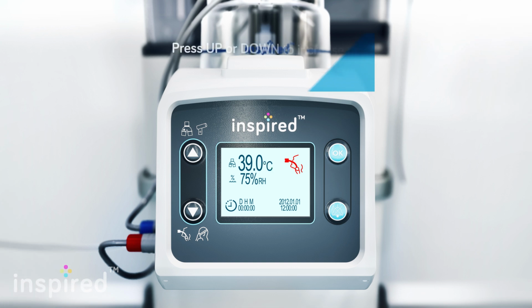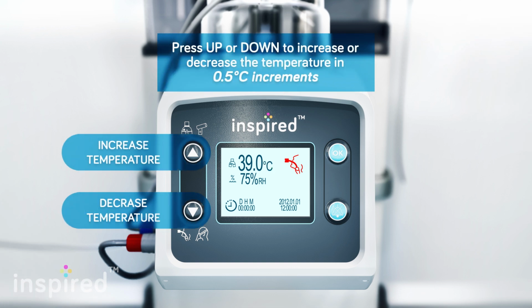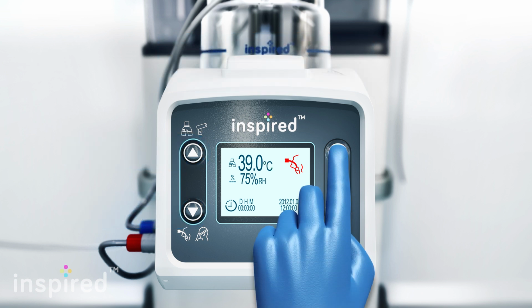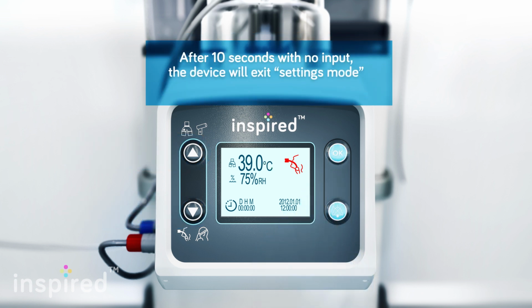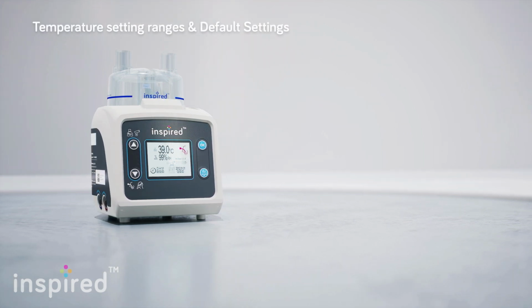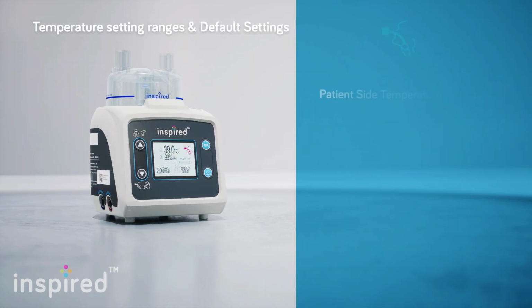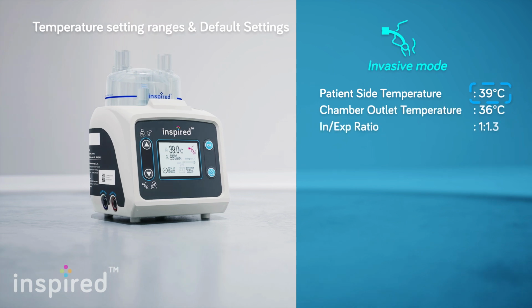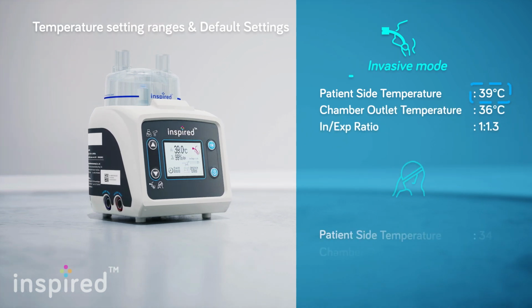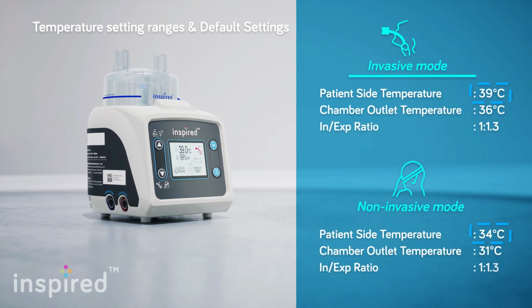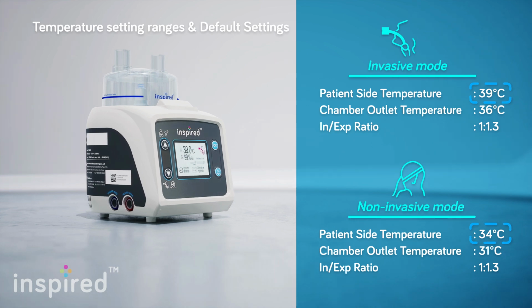Press up or down to increase or decrease the temperature in 0.5 degrees Celsius increments. Press OK to confirm. After 10 seconds with no input, the device will exit settings mode without saving the changes. The temperature setting ranges and default settings are as follows. The default temperature is 39 degrees Celsius for invasive mode and 34 degrees Celsius for non-invasive mode.